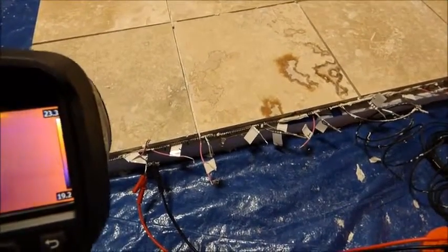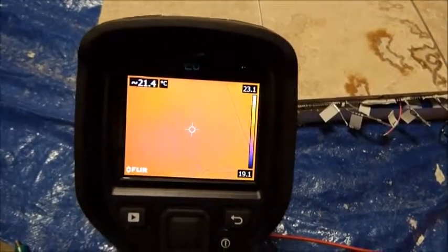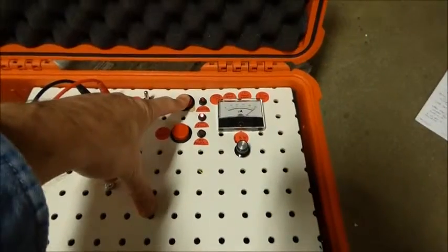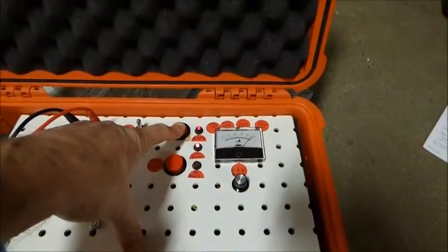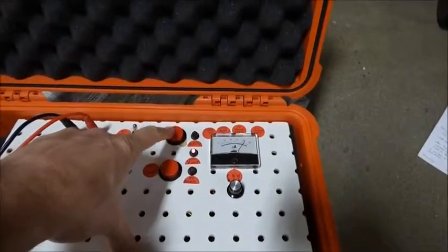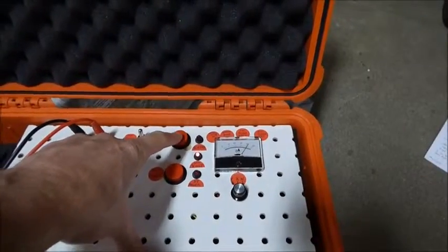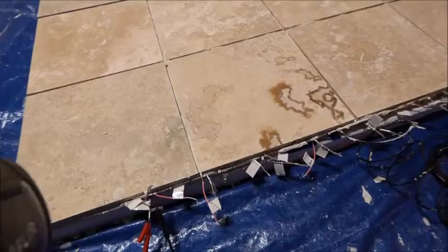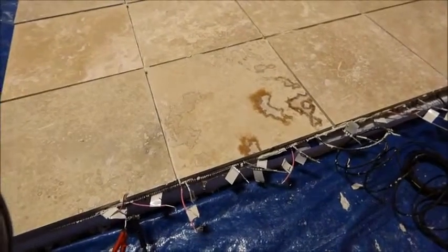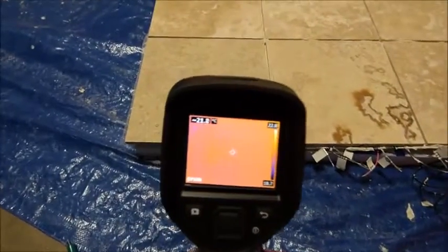Alright, I'm not really seeing anything here. So we're not really getting much of a response. Why not? Because I can't create a hot spark, and because this device can really only run about 2 amps, which is a pretty healthy amount of current. And 2 amps through that ground fault isn't heating the wire up enough to see it.